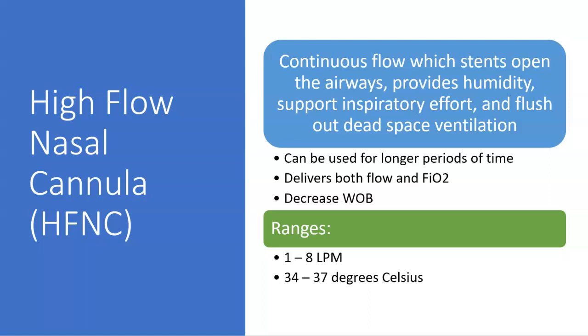We can't call it PEEP because we're not measuring it with a pressure, and we can't really say we have a set pressure. But it helps stent open the airways. It provides humidity. We can even give relative humidity. We can support inspiratory efforts because we're applying pressure that can support that inhalation.